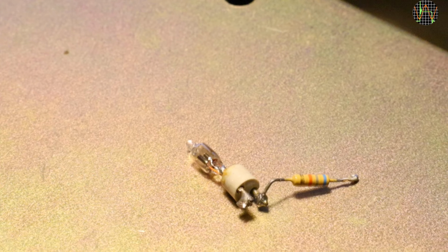This is more than 5.5 years if the machine was on permanently. It is quite possible that in a commercial lab, equipment may simply be left running permanently to avoid having to wait for any warm-up periods.